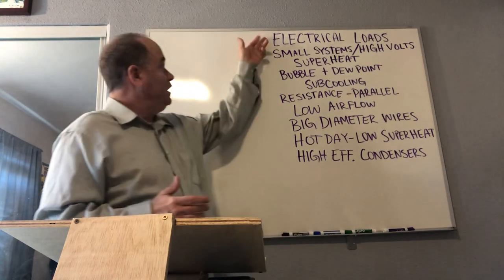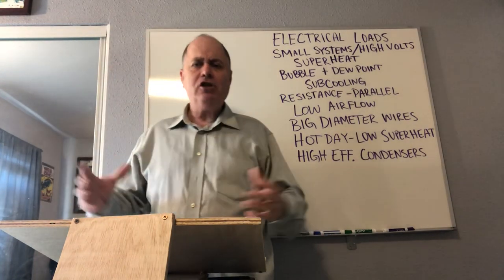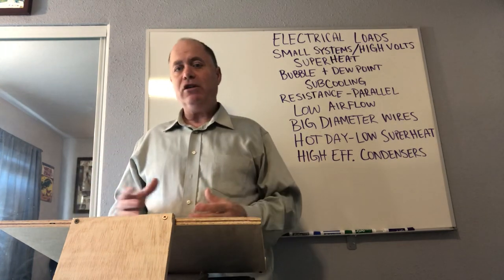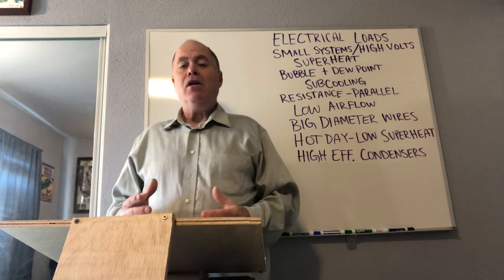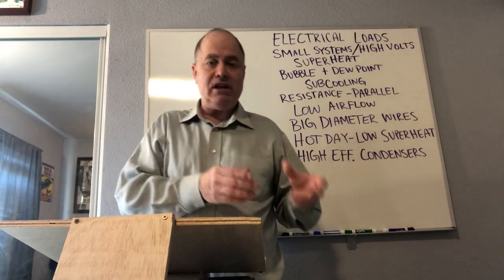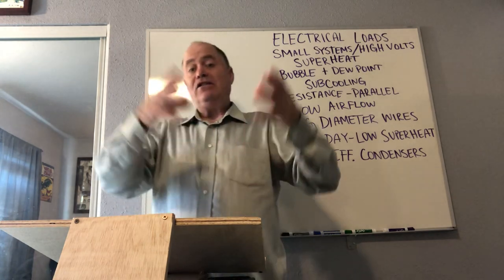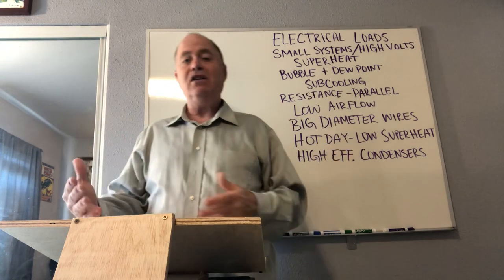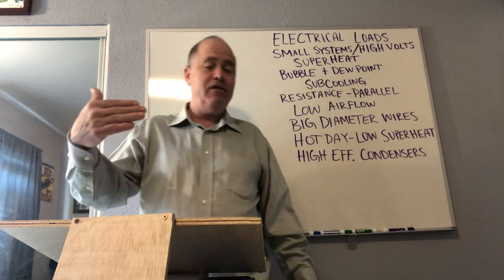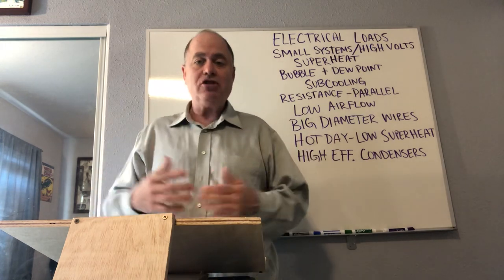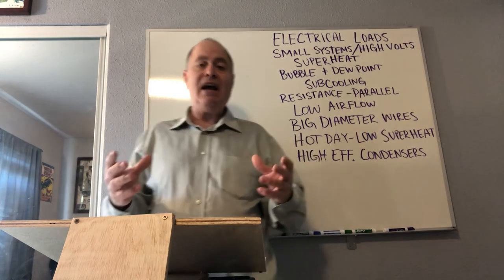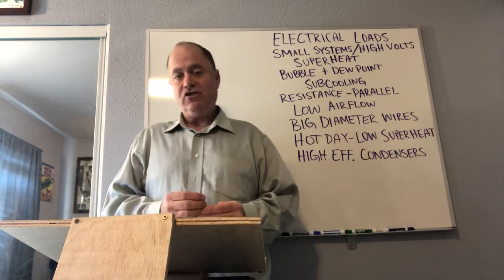First, let's start with electrical loads. Large electrical loads — big compressors, refrigeration and air conditioning compressors, large air conditioning fans — they have small resistances, low ohm readings, but they're really large electrical loads. They do a lot of work because the low ohms in the windings allow a lot of amperage to pass into the motor to actually do the work. So large electrical loads actually have small resistance readings.